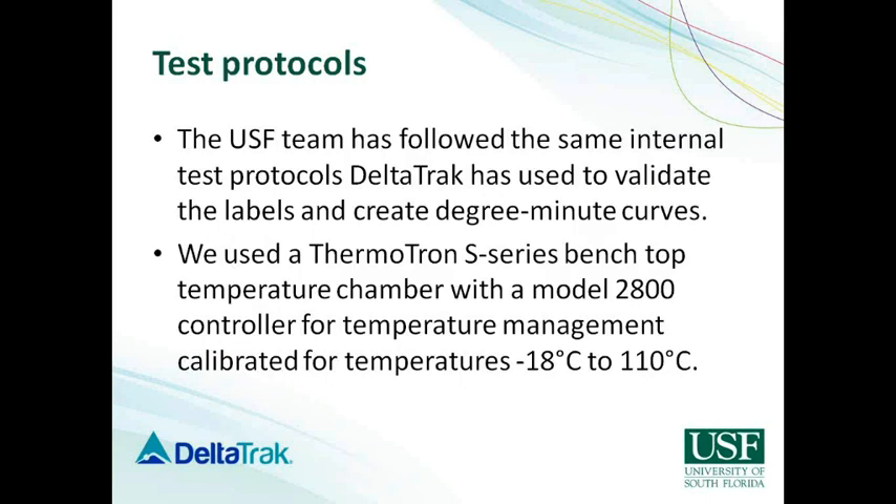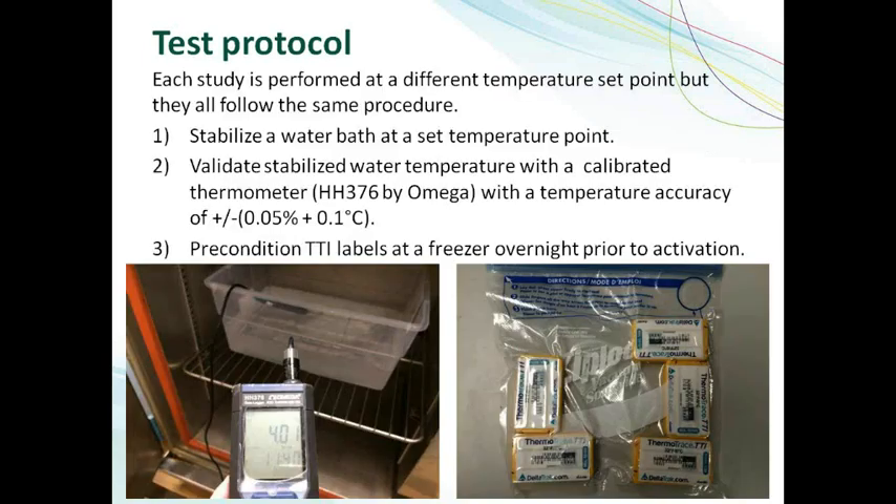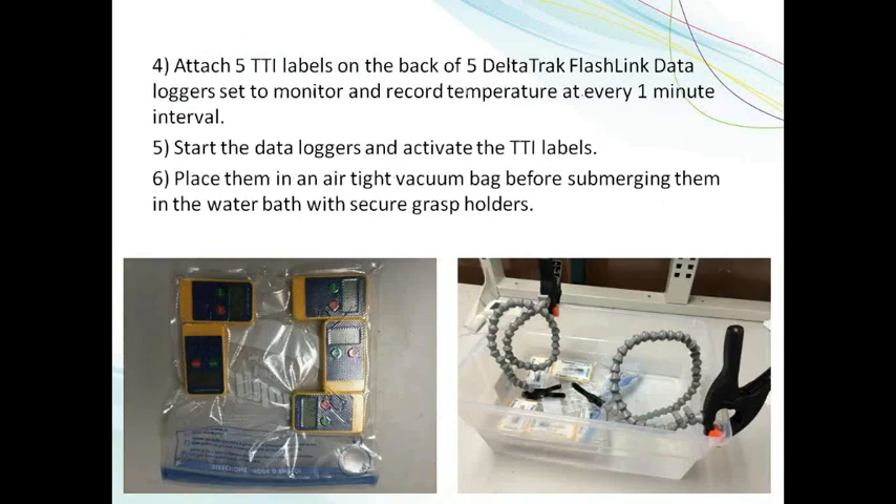For the test protocols, we used similar protocols to DeltaTrak's internal testing to validate these labels and to create the degree-minute curves at different temperatures. In the lab, we had a ThermoTron S-Series benchtop temperature chamber with a 2800 controller. This chamber is validated for a wide range of temperatures ranging from minus 18 degrees Celsius all the way up to 110 degrees Celsius. The protocol is very simple: the first thing is to stabilize the water bath at that set temperature point. To do that, we leave the water bath in the chamber for a prolonged period of time, and then we measure the water temperature using a calibrated thermometer. This is important because the temperature chamber sensors might be at different locations, so we have to make sure the water temperature is at the point we want.